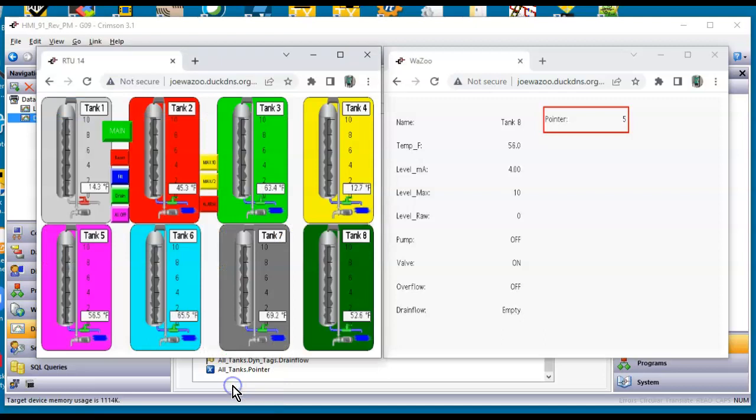Let me look at something. If I go to the PLC, they are all empty except for this one. I bet it doesn't show because these guys all have the valves open, but this one doesn't. So if I put this on tank 1, that is absolutely correct. If you come to one of my virtual classes or real classes in person, you'll know what's going on there because of that sensor design. You'll know that the valve has to be opened for the sensor right here to indicate water flowing by. Anyway, let me click the all off here, which should close all the valves.